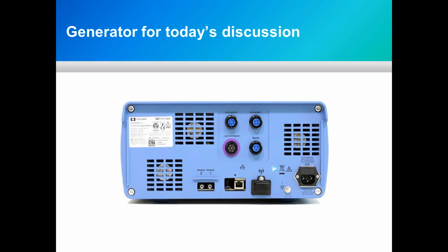As we switch over and look at the rear of the unit, you'll see that there are just 4 foot switch connectors: the 4-pin associated with Monopolar 1, and this pretty much aligns with the segments on the front display. Monopolar 2 is the 6-pin, and of course the 2 additional pins have to do with the Valleylab mode. The Bipolar, the same 3-pin as you've used previously. LigaSure, there is only 1 foot switch connector now, the purple one. The orange one is not there.